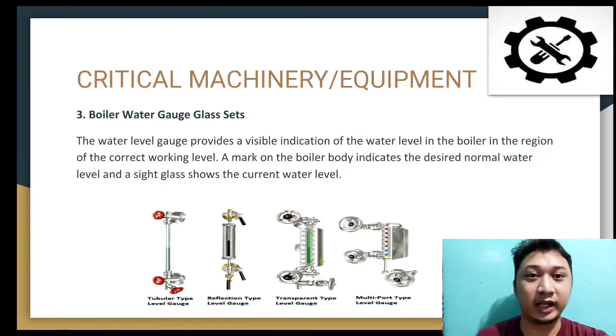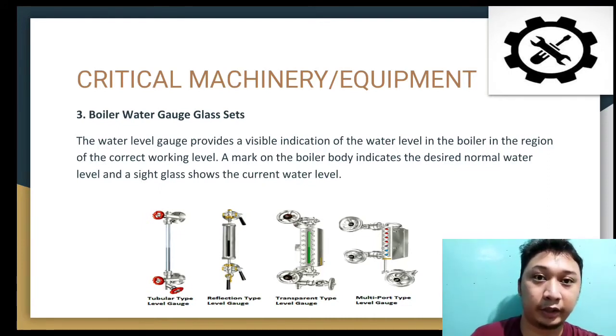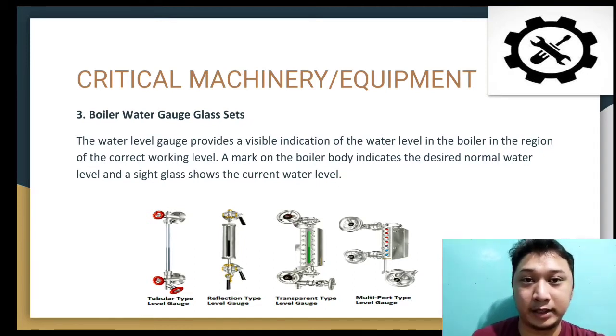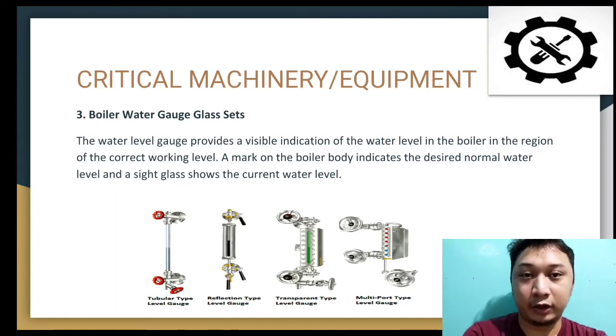Hi everyone, by the way, I'm Engine Cadet Navarro, and I will be continuing to report the critical machinery equipment. As you can see in the PowerPoint, I will be discussing number 3 of the critical machinery equipment, and number three is all about the boiler water gauge glass sets. In this boiler, the water level gauge provides a visible indication of the water level in the region of the correct working level. A mark on the boiler body indicates the desired normal water level, and a sight glass shows the current water level.